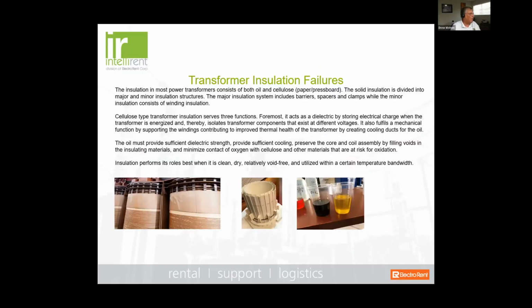Now, when we talk about insulation failures, the insulation in most of your power transformers consists of both oil and cellulose, which of course is paper and pressboard. The solid insulation is divided into major and minor insulation structures. Your major insulation systems include barriers, spacers, and clamps, while your minor insulation consists of the winding insulation, the paper, and the polymers. Cellulose type transformer insulation actually serves three different functions. It acts as a dielectric by storing electrical charge when the transformer is energized, and isolates transformer components that exist at different voltages. It also fulfills a mechanical function by supporting your windings and contributing to improved thermal health of the transformer by creating cooling ducts for the oil.